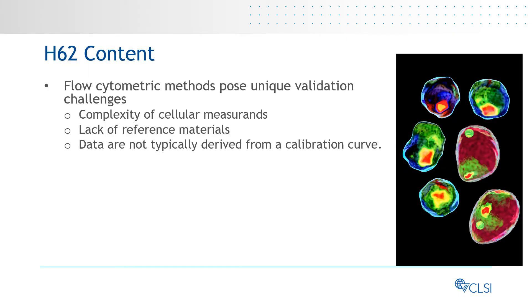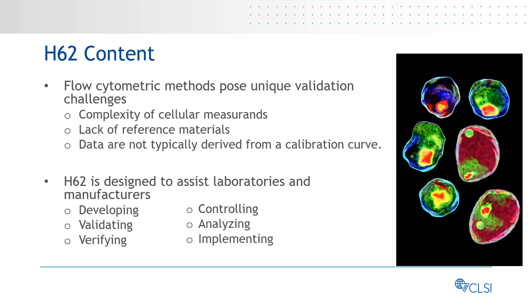Flow cytometric methods pose unique validation challenges due to the complexity of cellular measurements, the lack of reference materials, and because data are not typically derived from a calibration curve. The H-62 content is designed to assist laboratories and manufacturers in developing, validating, verifying, controlling, analyzing, and implementing cell-based flow cytometry tests.